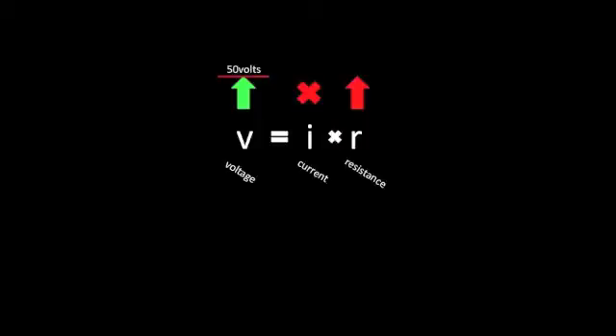The transmitter's maximum voltage limit is 50 volts. If you're at 50 volts and the current is still very low, this would be a time to try a higher frequency or take measures to improve the ground for lower resistance.